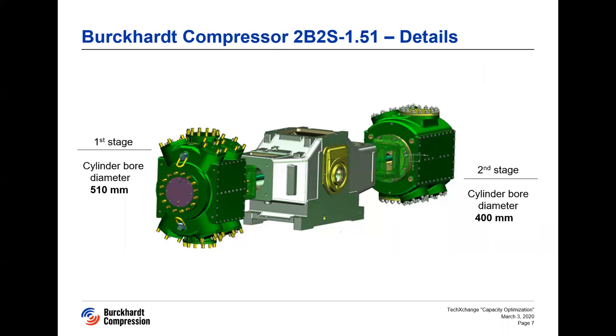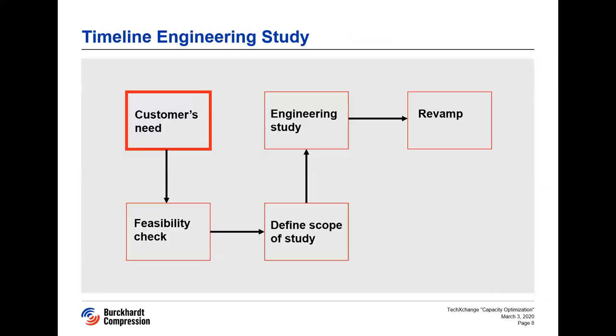The original cylinder bore diameters of the first and second stages were 510 and 400 millimeters respectively. This project is elucidated from when the client got in contact with Burckhardt Compression to find a solution for their needs — through the approach we took involving feasibility checks, engineering study, and finally the revamp carried out to achieve the final goal.